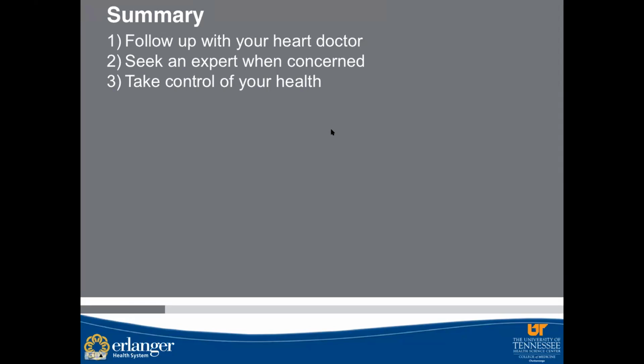The follow-up schedule is usually within 1 to 2 weeks after the device is put in to make sure the wound is okay, and then every 3 months from then on. At those 3-month intervals, what most people do is one check is done from your home, and the subsequent 3-month check is done in the office. We can detect lead failures through either of those transmissions most of the time. By detecting that, we would take further action, let you know, and go from there.